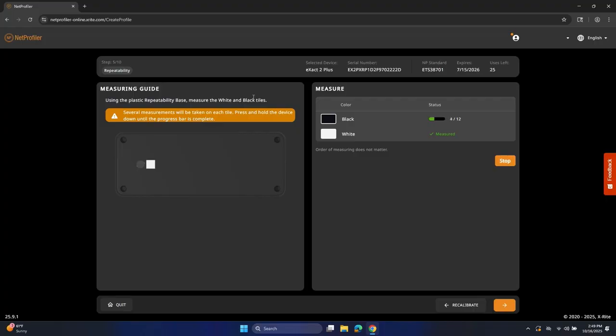What we're doing with these measurements is validating: can this instrument repeatably measure white? So we're testing all of the white measurements against themselves, and the same with the black, to see if the instrument can repeatably measure the same color. Because if we can't pass this, there's no point in profiling, because it means that the device has some issue with measurement, right? So it's a repeatability test.